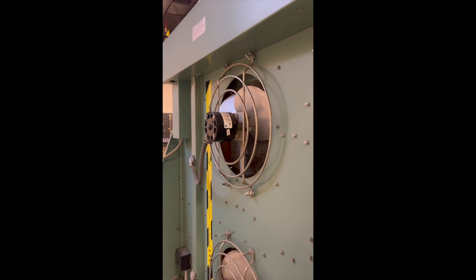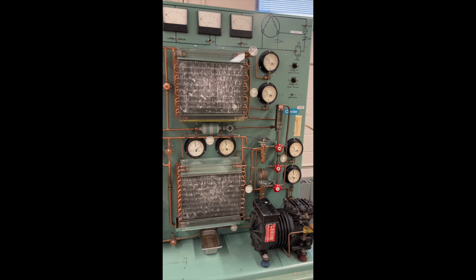Furthermore, if we want to assess the performance of these heat exchanger units, I mean the condenser and evaporator, we need to have information about the incoming air, as you can see, using a forced draft fan device here, and the outcoming air from the front face of the condenser and evaporator. We need to measure the specifications of the input air and output air. So we need a couple of devices that I'm going to introduce to you here.